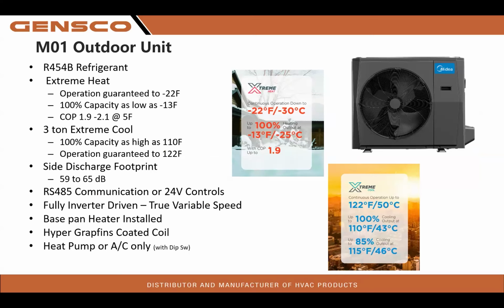The refrigerant we are using is 454B. All of our models are extreme heat. We have dual communication modes, RS-485 communication with the TL04 stat, or you can choose to go standard conventional 24-volt controls. And you can use any thermostat you want on this, okay? I do not recommend using 24-volt controls. I would prefer that everybody use the Midea TL04 stat, fully communicating.